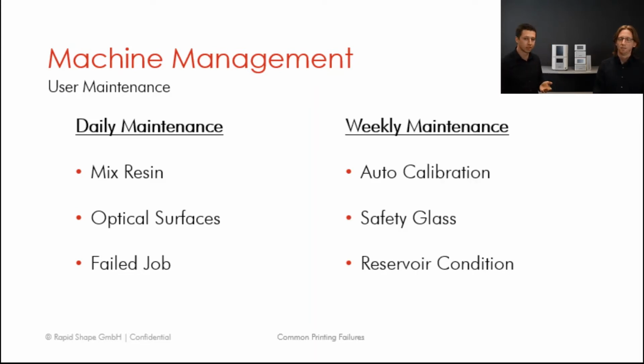Then there's the weekly maintenance. You should, as always recommended, do the auto calibration once a week. It was presented in one of the webinars how to do the auto calibration. Next step is to also check the safety glass weekly, really. Check if there are scratches, other damage, or cured material on it, to prevent unexpected results. The same goes for the reservoir condition. In the reservoir there's a glass on the bottom and the Teflon foil on top. Both of them should be clean and not damaged in order to get the best results we can.